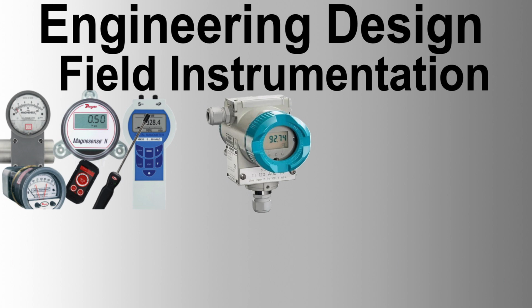2-valve manifold for pressure gauges and pressure transmitters, 5-valve manifold for differential pressure transmitters. Instrument manifolds must be machined from a single bar stock of SS316 material. Valve seats, stem, and union bonnet must be of 17-4 PH material. Valve packing material must be in accordance with the design pressure rating of the service. The valve seats must be of hard, self-aligning type with non-rotating tip.